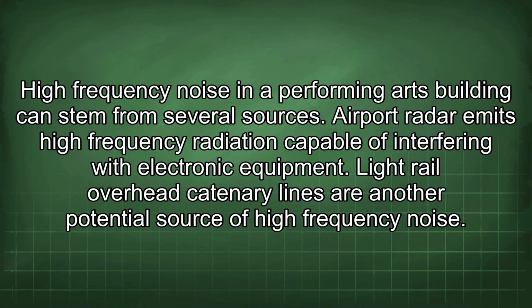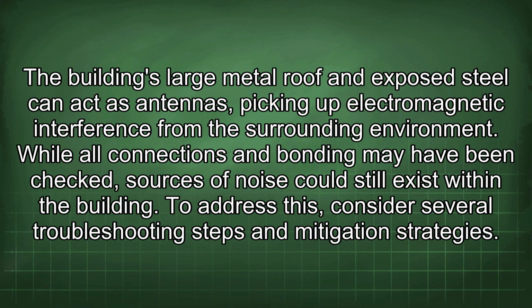High-frequency noise at a performing arts building can stem from several sources. Airport radar emits high-frequency radiation capable of interfering with electronic equipment. Light rail overhead catenary lines are another potential source of high-frequency noise. The building's large metal roof and exposed steel can act as antennas, picking up electromagnetic interference from the surrounding environment.